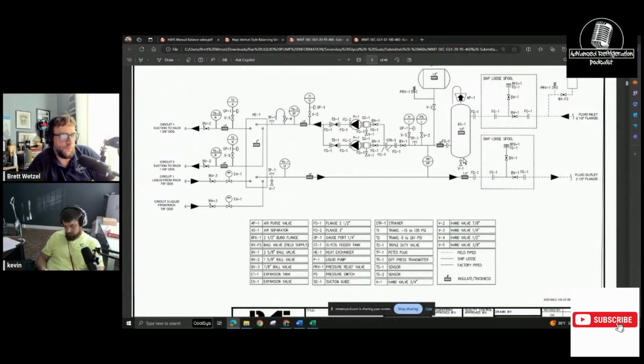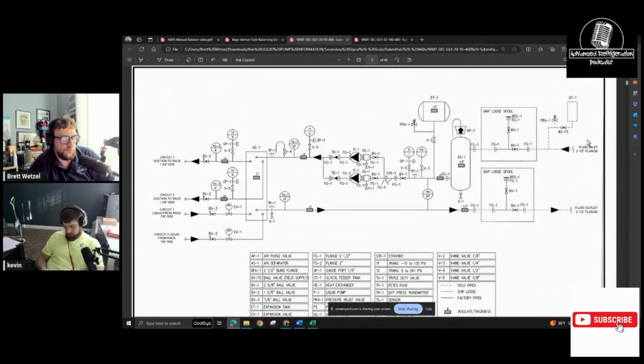So the only thing that I really didn't dig, and we brought this up to him: there's your air glycol separator, and there's your expansion tank. The thing that's wonky is that there is no catch for the actual pop-off for the bleed. On some of the other racks that we're accustomed to, that the Big W used to do a long time ago, you at least had a catch for that, and that's usually where your fill is. There's actually a fill station downstairs. It's that GT1 right there, the glycol fill, and it's something I've never seen before. And I love those things.